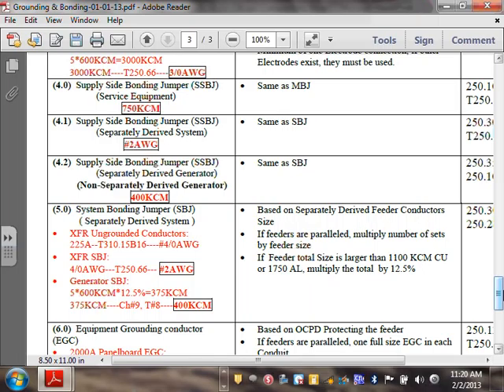Okay, here's my transformer. I size a transformer, guys, and I tie my transformer to a 225 amp panel. If you size the feeders to feed a 225 amp panel, what do you get? 4-aught. So my feeders coming out of the transformer to the 225 amp panel are 4-aught. So you take the 4-aught now to 250.66. What's the main bonding jumper? The system bonding jumper is number 2. That's how we size it. The system bonding jumper.